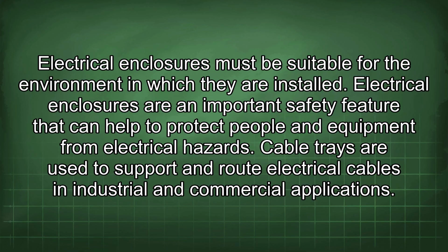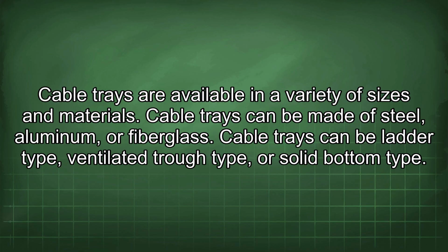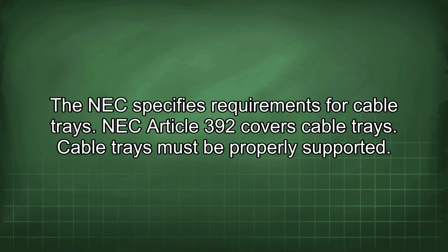Cable trays are used to support and route electrical cables in industrial and commercial applications. Cable trays are available in a variety of sizes and materials. Cable trays can be made of steel, aluminum, or fiberglass. Cable trays can be ladder type, ventilated trough type, or solid bottom type. The NEC specifies requirements for cable trays. NEC Article 392 covers cable trays.